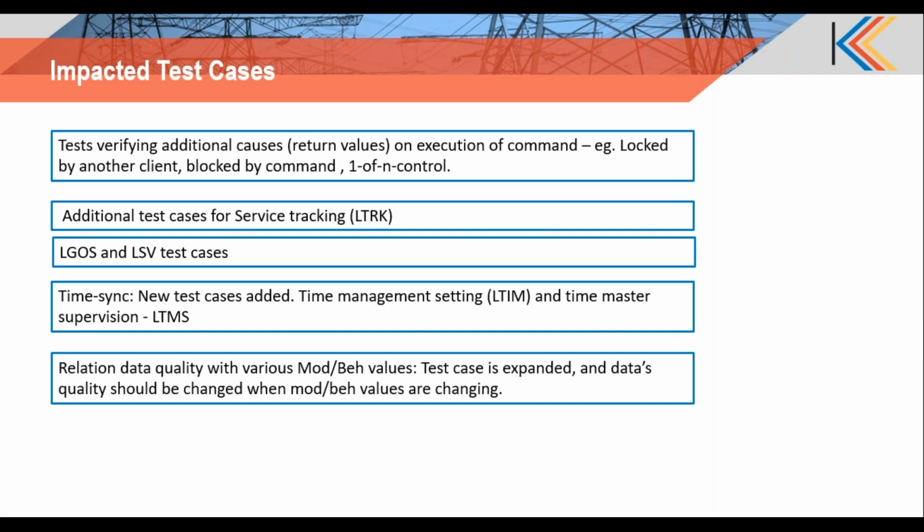Then similarly, we have the LTRK additional test cases, LGOS and LSV, there are additional test cases, and time sync is another area of importance. Now, time sync has been a mandatory test, and also we have this LTIM, the time management setting and time supervision, time master supervision, new logical nodes being added in 61850 Edition 2. So there will be additional tests associated with that.